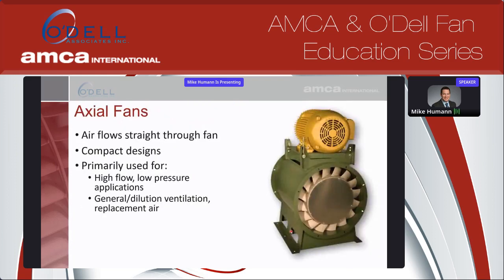When you get to axial fans, these tend to have compact designs, usually duct mount fans, or you'll see them for exhausting up on roofs, or even bringing air into buildings from the roof. Usually a high flow, low pressure application. The air flows straight through the fan. We don't actually bend it like we do with a centrifugal fan.